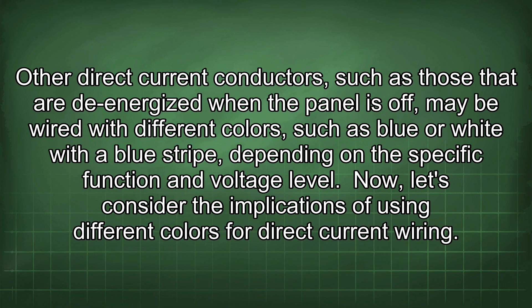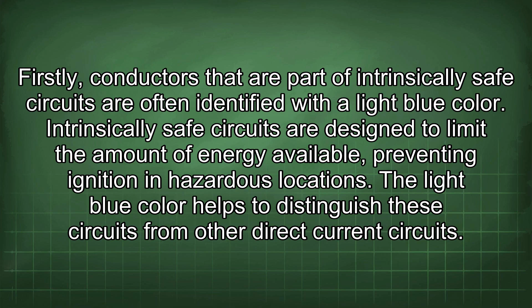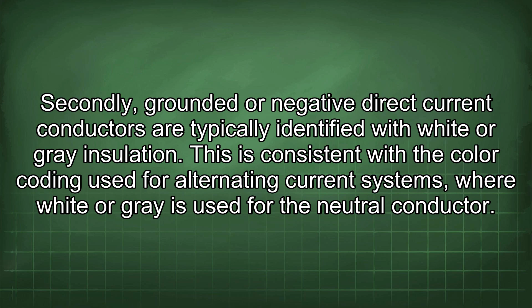Firstly, conductors that are part of intrinsically safe circuits are often identified with a light blue color. Intrinsically safe circuits are designed to limit the amount of energy available, preventing ignition in hazardous locations. The light blue color helps to distinguish these circuits from other direct current circuits. Secondly, grounded or negative direct current conductors are typically identified with white or gray insulation. This is consistent with color coding used for alternating current systems, where white or gray is used for the neutral conductor.